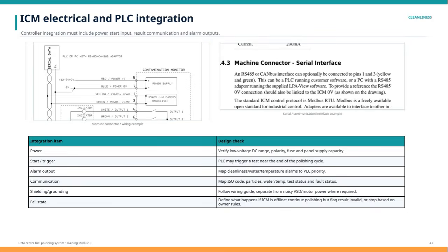Here, we're focusing on the critical aspects of integrating the ICM electrical system with the PLC. Integration starts with ensuring the controller includes power connections, start inputs, communication for results, and alarm outputs. Cleanliness is also a vital consideration to maintain system reliability. Looking at the integration details, we first verify the power supply for low-voltage DC range, correct polarity, proper fusing, and adequate panel capacity. The start or trigger signal is often controlled by the PLC, which may initiate a test near the end of the polishing cycle to ensure timely operation. Alarm outputs play an important role by mapping cleanliness, water levels, and temperature alarms to the PLC's priority system, allowing for immediate response if any parameters fall outside acceptable limits.